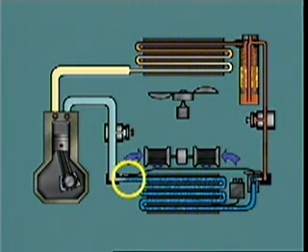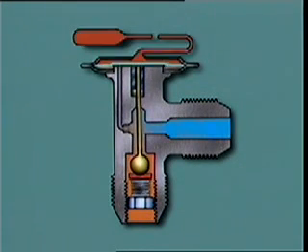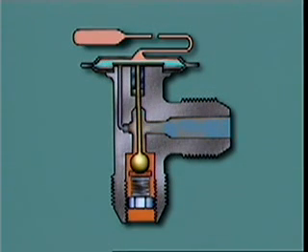The temperature at the evaporator outlet determines the pressure in the bulb. Higher temperatures will give higher pressures and this will tend to open the valve wider and allow more refrigerant to flow through. Lower temperatures will give lower pressures. This will tend to close the valve and reduce the flow of refrigerant.